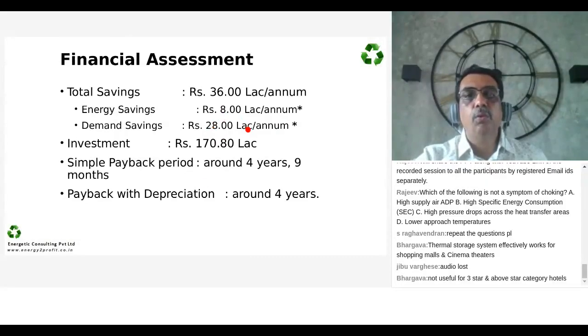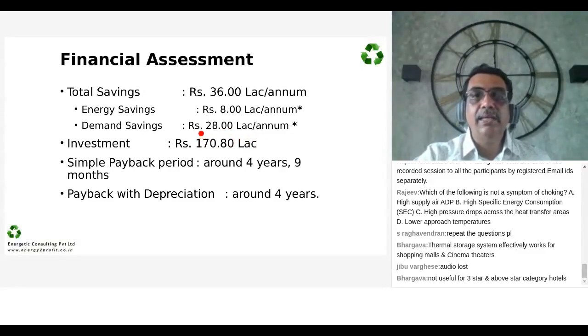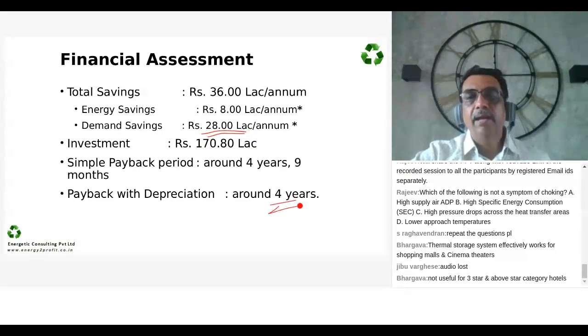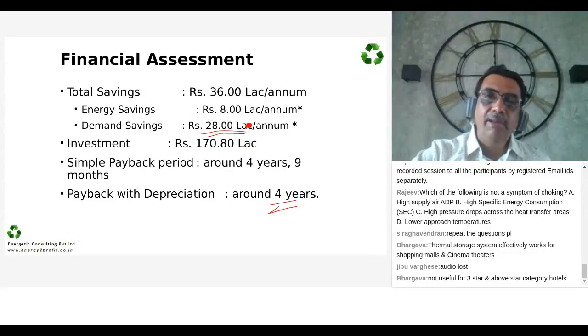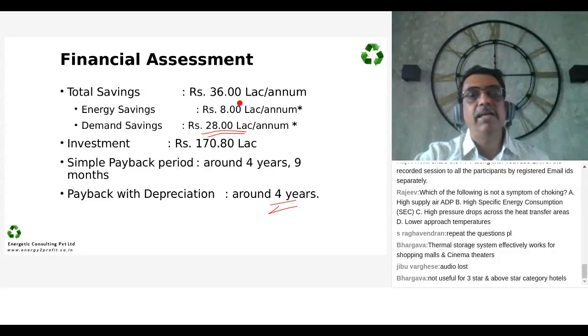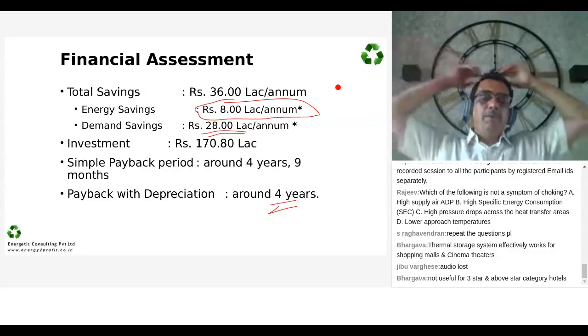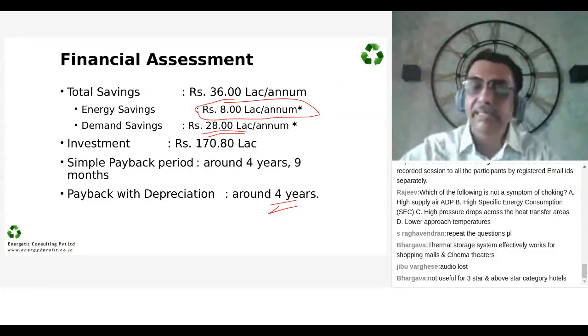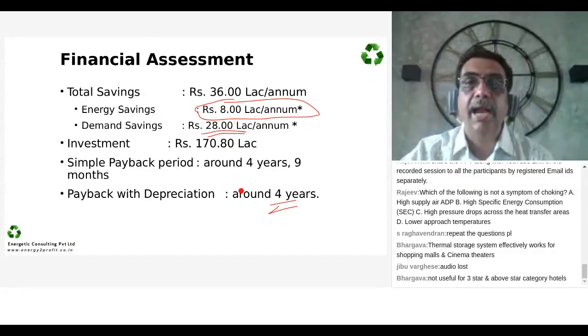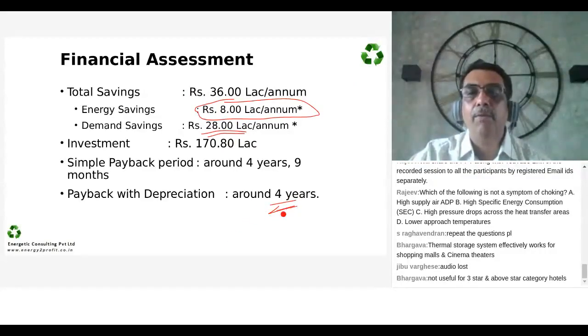This is the total saving. About 1.8 CR was the investment. You see, demand saving was major. And the payback was 4 years. And at the time when it was implemented, there was no advantage on time of the day tariff. So this energy saving, whatever is seen here, is only on account of pumping energy saving. Time of the day savings were not seen then, which get added today. And still the payback was around 4 years.